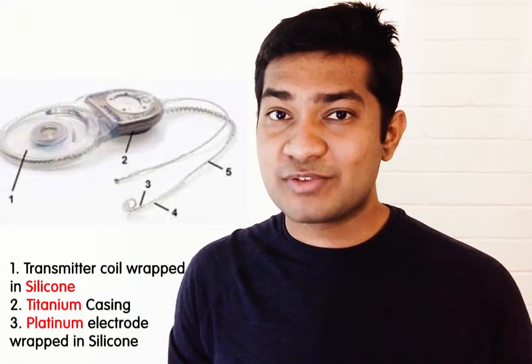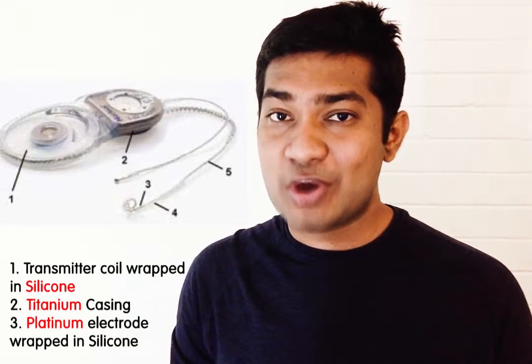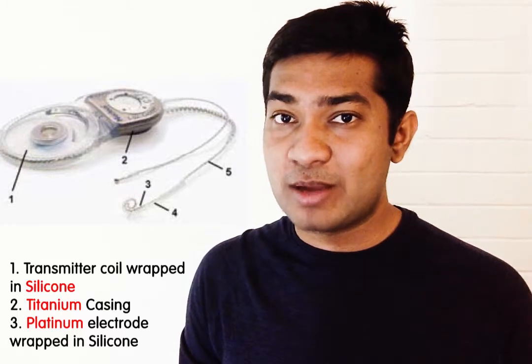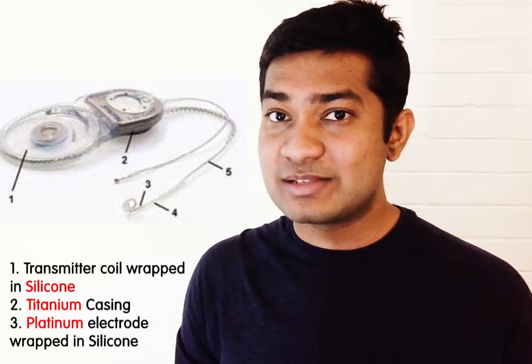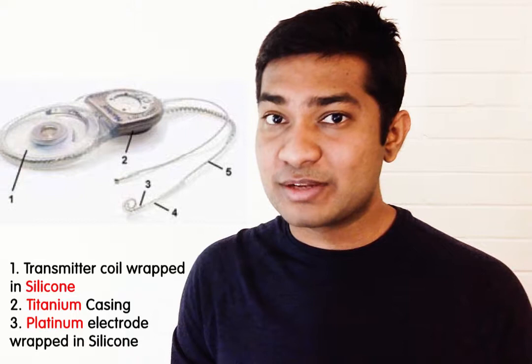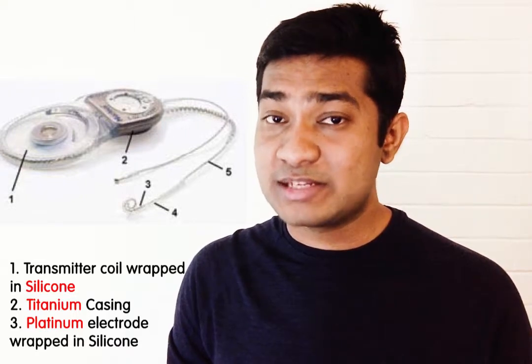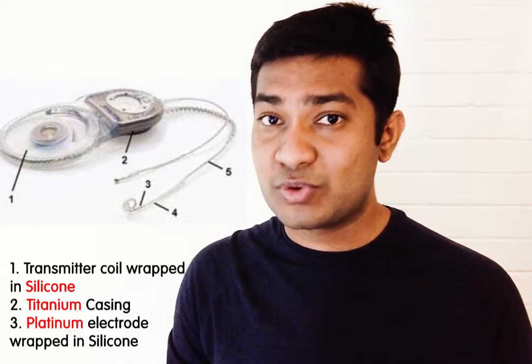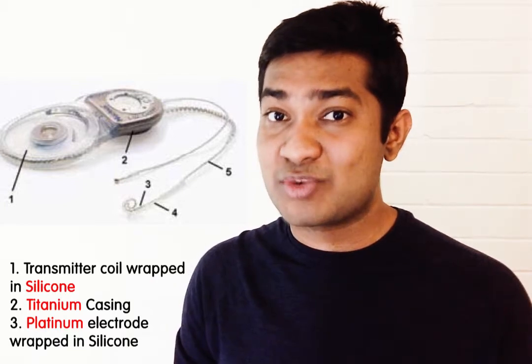It consists of a transmitter coil that is wrapped in silicone, showcased as number 1. Number 2 is a titanium casing to enclose the electronics used in the implant. And number 3 is the platinum electrode embedded in silicone that runs straight to the cochlea. The electrode plays a crucial role as it has to penetrate into the cochlea, and it also has to ensure no tissue formation around it.